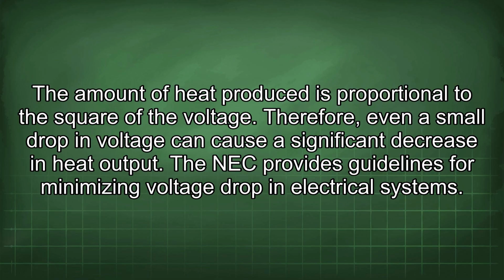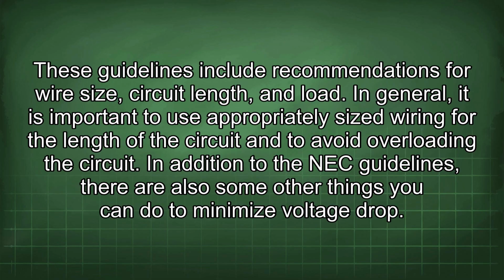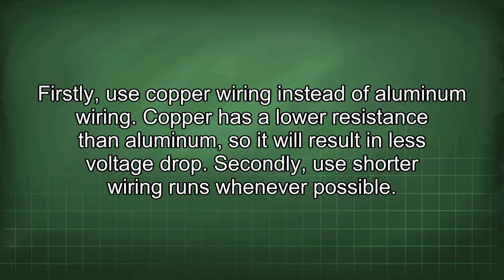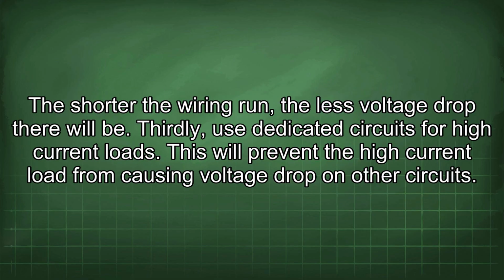The NEC provides guidelines for minimizing voltage drop in electrical systems. These guidelines include recommendations for wire size, circuit length, and load. In general, it is important to use appropriately sized wiring for the length of the circuit and to avoid overloading the circuit. In addition to the NEC guidelines, there are also some other things you can do to minimize voltage drop. Firstly, use copper wiring instead of aluminum wiring. Copper has a lower resistance than aluminum, so it will result in less voltage drop. Secondly, use shorter wiring runs whenever possible. The shorter the wiring run, the less voltage drop there will be.